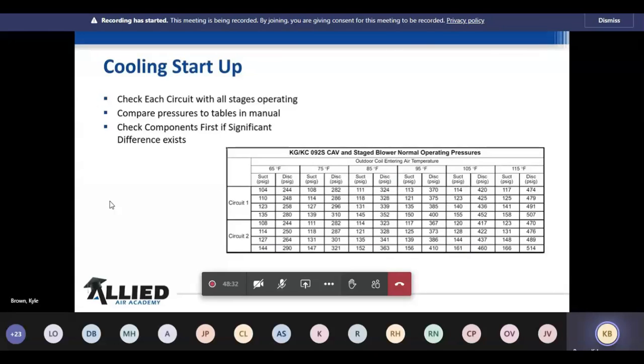And then you can go by this, but don't take these numbers all the way to heart, because this is a perfect scenario, perfect CFMs, perfect static pressure, and a perfect lab setting. And we all know the world we live in and work in is not that way. But this gets you in the ballpark. This gets you in a range. So I'm just going to take the first 2 numbers at 65 degrees, 104 and 244. So if I'm running 257 on my head pressure, I'm not going to be alarmed. I'm not going to worry about that. Or if it's hot down there and I'm running 115 on my suction pressure, I'm not going to worry about that. Or if it's cool downstairs and I'm running 99 to 101, I'm not going to worry about that either. Okay, that's where we have to understand the variables and a little bit of flexibility on this.